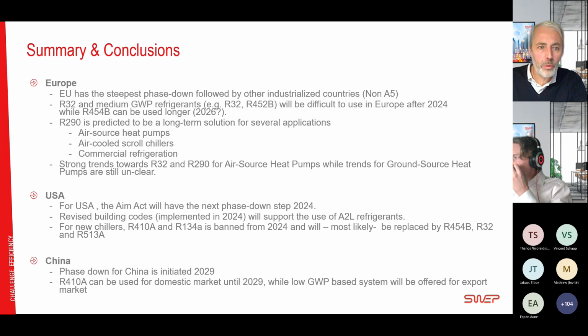R290 propane, we predict that to be a long-term solution for several applications, especially air source heat pumps, air-cooled chillers, and commercial refrigeration, where it's already widely used. We see very strong trends towards R32 and R290 for air source heat pumps, while the trends for ground source heat pumps are still unclear. And just a comment here, the reason is, of course, that air source heat pumps are placed outdoors, and it's much easier to mitigate the risk of flammable refrigerants compared with bringing it indoors.